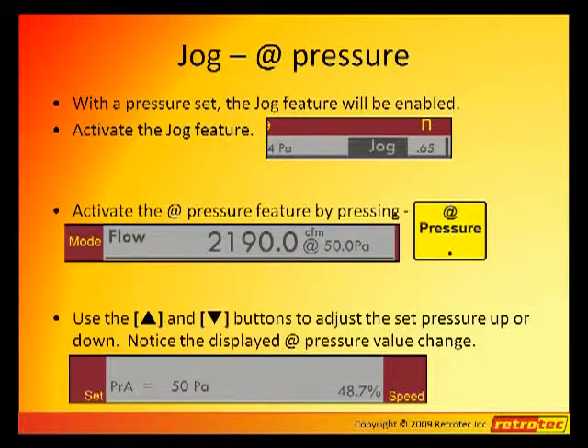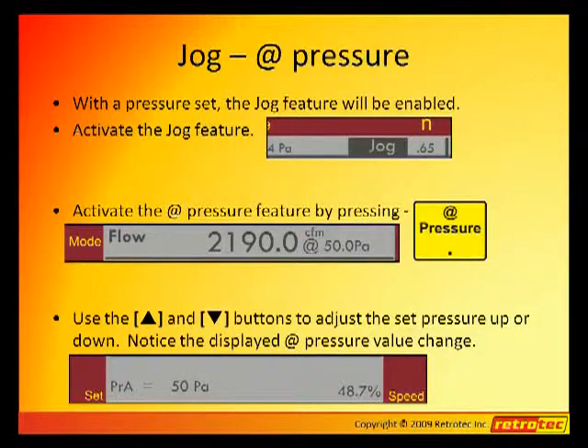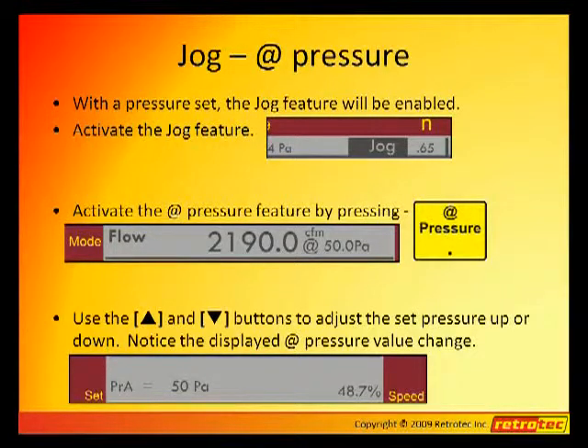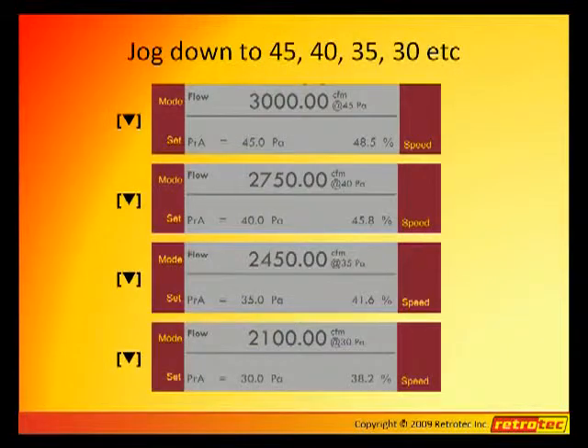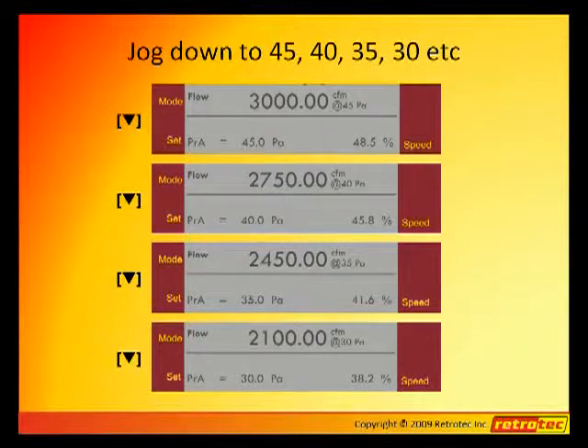If we set the pressure to 40, then the extrapolation pressure will also be 40. This will allow you to take extremely rapid readings when taking data for a multipoint test, almost as fast as you can click the down arrow and write the numbers down. Because in each instance, the gauge is automatically extrapolating to exactly the pressure that you wish to achieve, even though you may not have reached it yet. Here we see the pressure gauge jogging down from 45, 40, 35, and 30, each step accomplished by hitting the down arrow once.